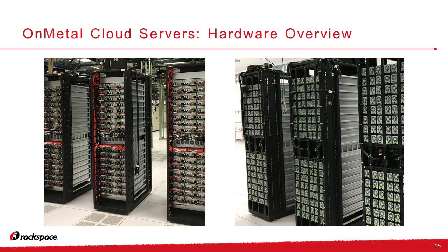In addition to the fans, which tend to have a fairly low failure rate, we've also made the power highly available, in an N-1 availability pattern. You can see the power distribution bars in the picture on the left in the center of the cabinet design. What that allows us to do is not only increase efficiency of power transfer, taking direct current directly to the servers, but it also allows us resiliency at the power supply level, in addition to the dual source A-B power configuration we have running throughout our Rackspace data centers.